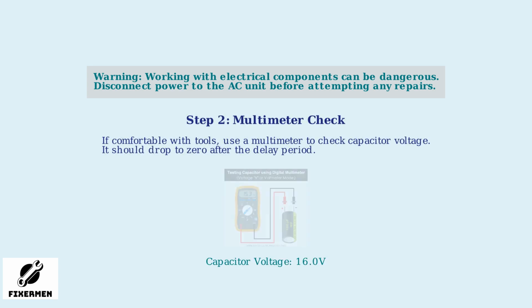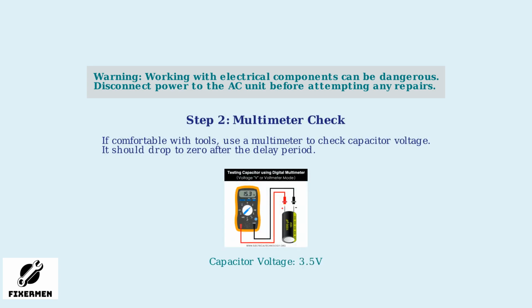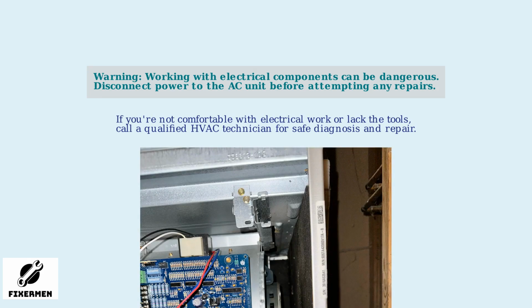If you have the skills and tools, use a digital multimeter to test the capacitor. Set the multimeter to voltage mode and measure across the capacitor terminals. During normal operation, the voltage should gradually drop to zero after the delay period ends, typically 3 to 5 minutes. Remember, working with electrical components requires proper knowledge and safety precautions. If you're not experienced with electronics or don't have the necessary tools, it's best to contact a certified HVAC technician who can safely inspect and replace faulty capacitors.